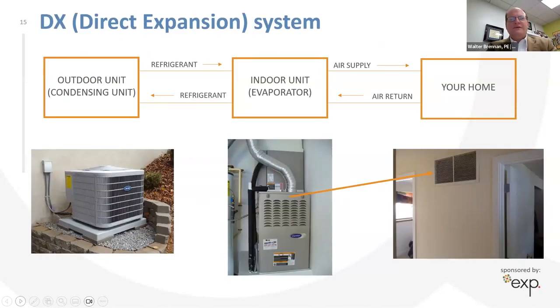At the fundamental level, a DX system, or direct expansion system, is basically what you find in your house. You have an outdoor unit called the condensing unit, and an indoor unit called the evaporator or fan coil unit. The air that comes from your house, from your living room for example, goes into that indoor unit, and we take the heat out of the airstream, then run that heat to the outdoor unit and discharge it to atmosphere. So a misnomer is that we don't actually do cooling necessarily, we actually do heat removal. Think of it that way and you'll understand every system.